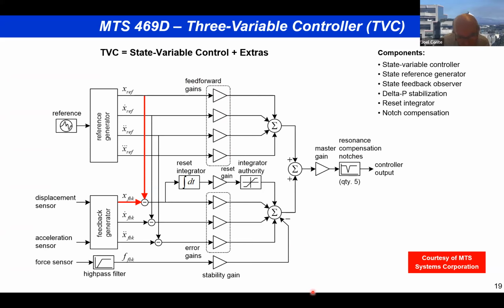And then in terms of the signal feedback, there is displacement feedback from each of the actuators, vertical and horizontal. There is acceleration feedback from the accelerometers installed on the platen, and the pressure transducer or force sensor feedback, right? So then the feedback generator part of the controller is using some composite filtering to produce the best estimate of the true feedback displacement, feedback velocity, and feedback acceleration of the platen. And then the control loop is closed on the displacement.